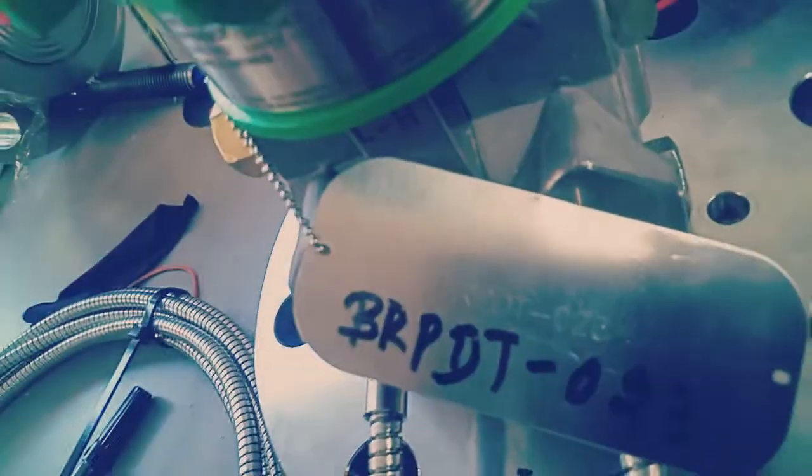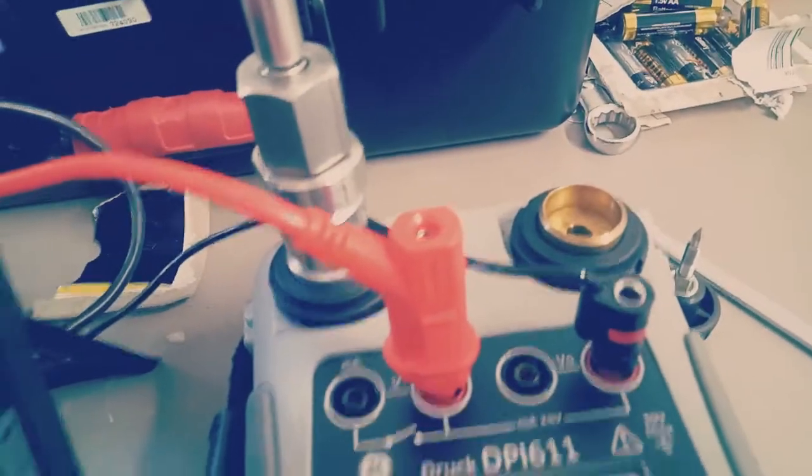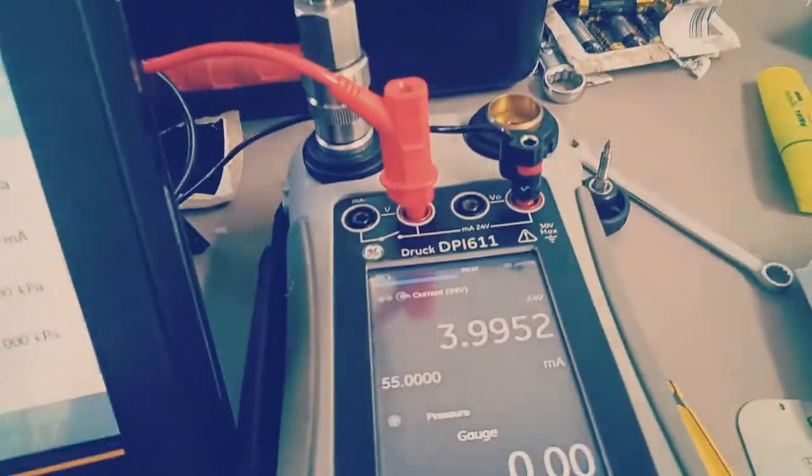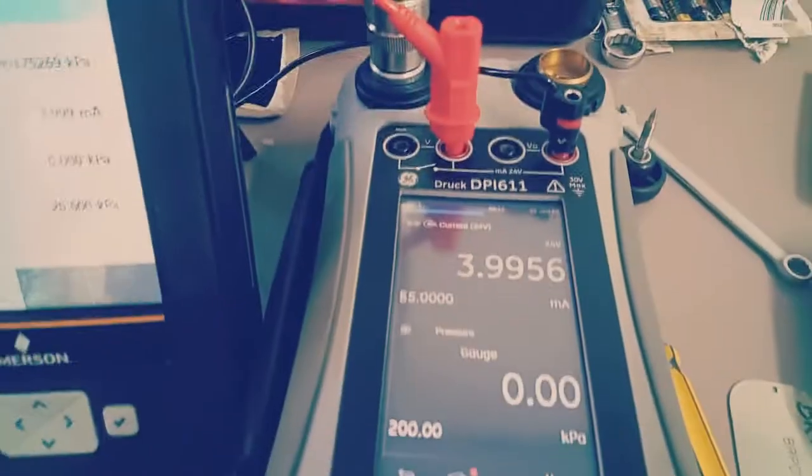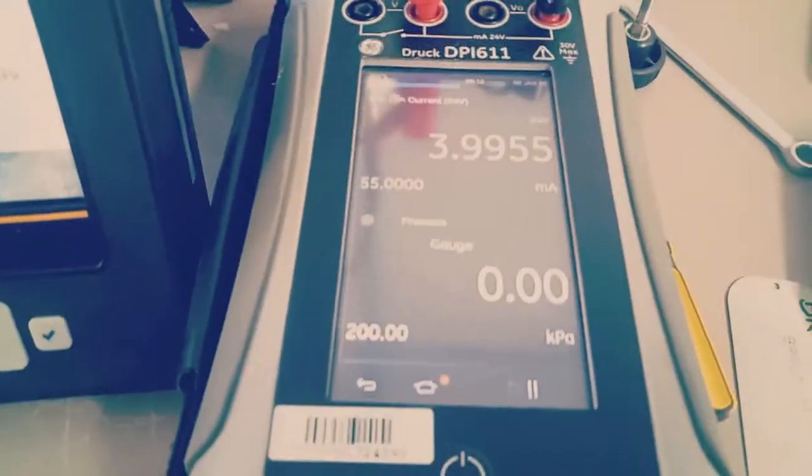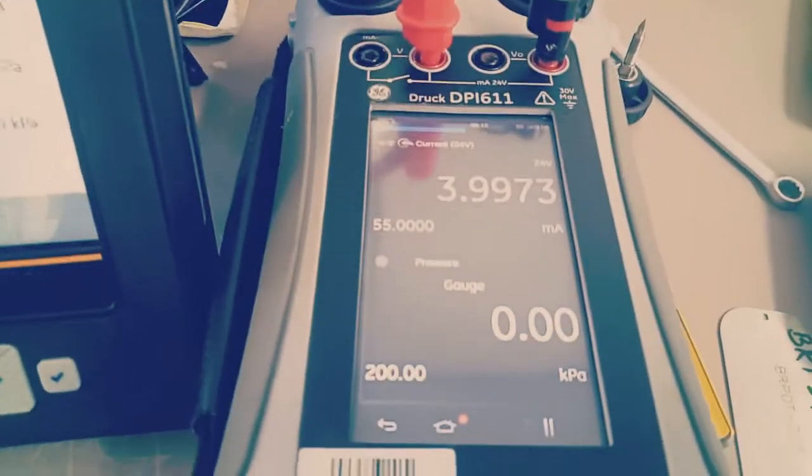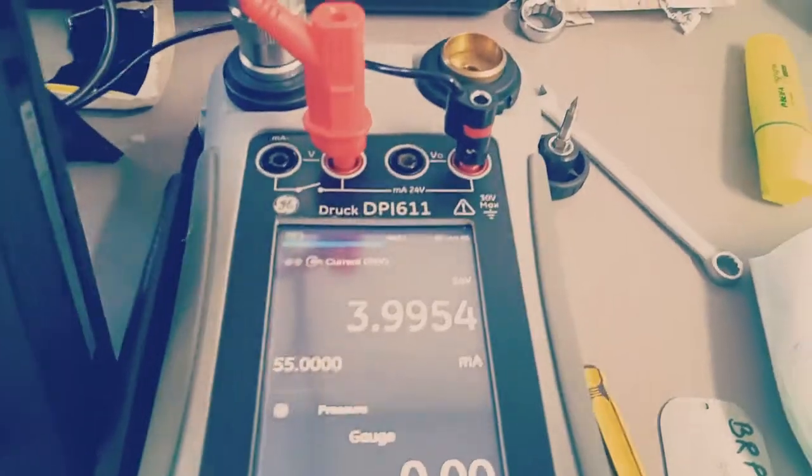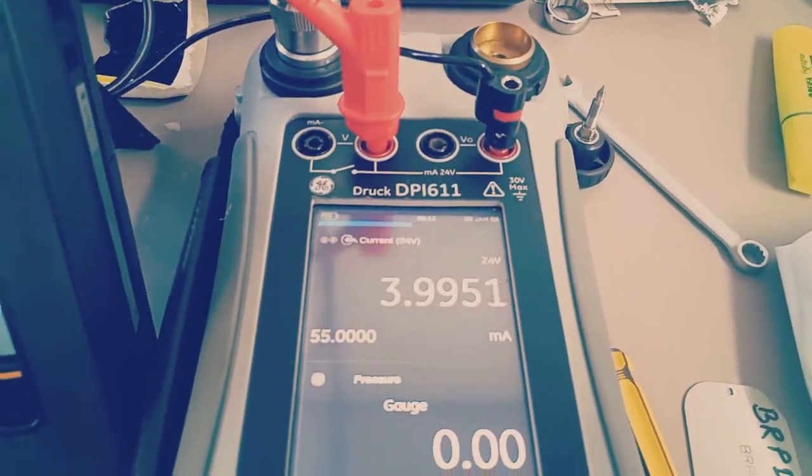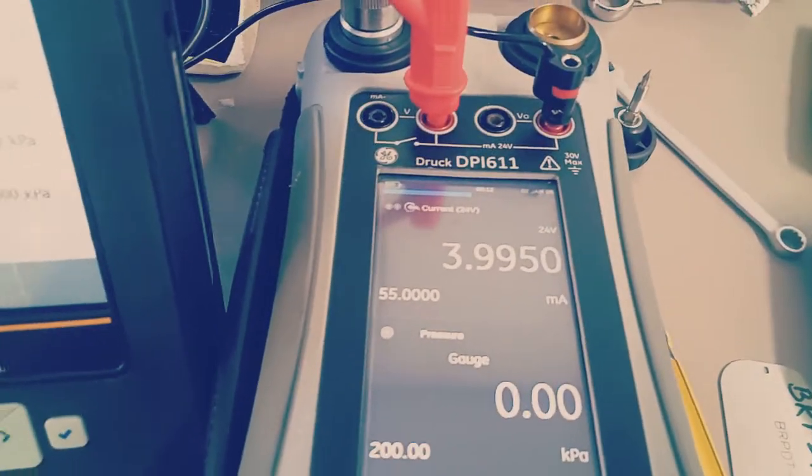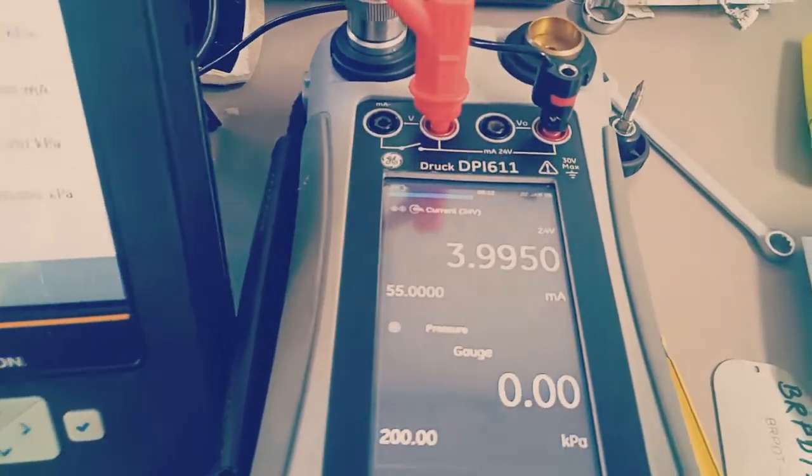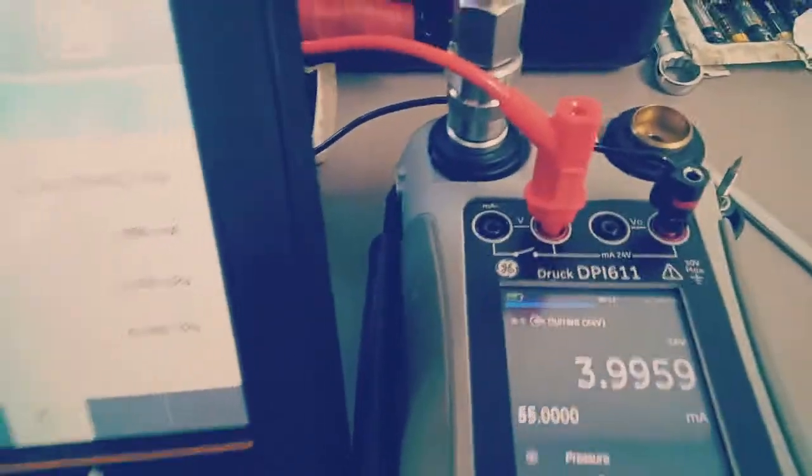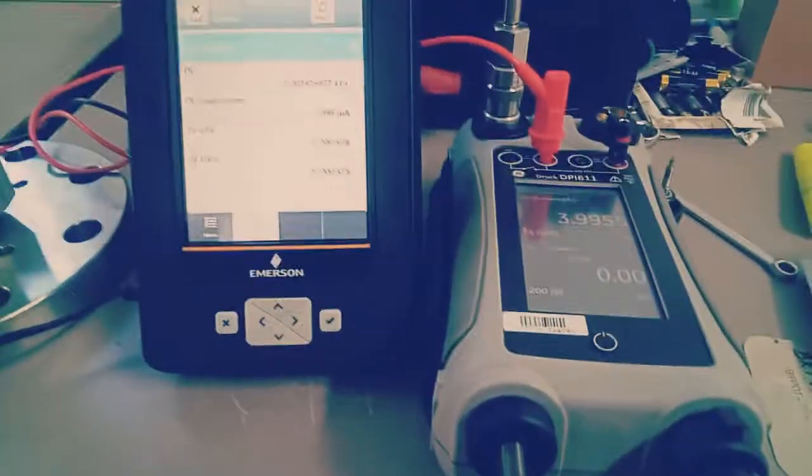The range of the transmitter is 0 to 200 kilopascal. Right now I have opened the pressure release port. It reads 0, the pressure is 0, and we get the milliampere 3.995, which is less than our tolerance. It is acceptable, so we go for 25 percent range.